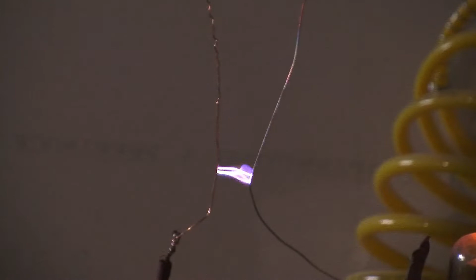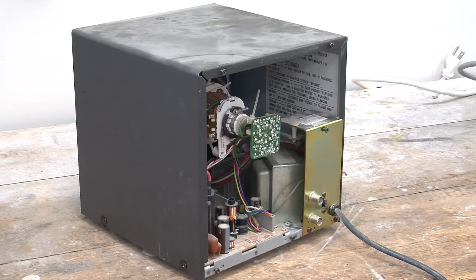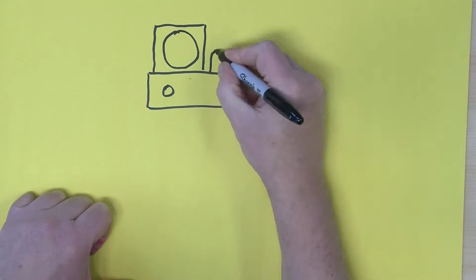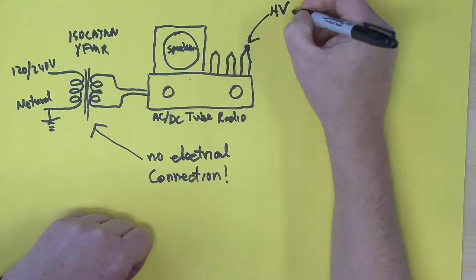The other thing that can happen is, imagine you're dealing with an electrical device and that device has a chassis, and the chassis is attached in one way or another to some of the circuitry, and you are probing various parts of the chassis, some of them at pretty high voltages. And while you're touching the chassis, you accidentally touch one of those high voltage points. Well, you will get zapped, and the isolation transformer won't be able to prevent that because the current is not going through you to ground, it's going from one hand to another.